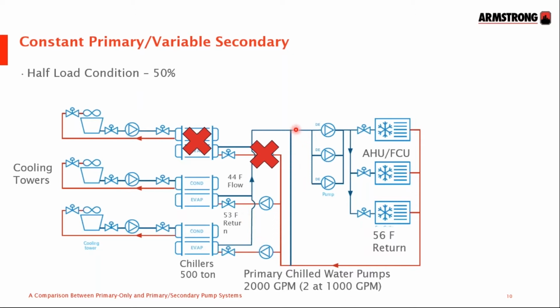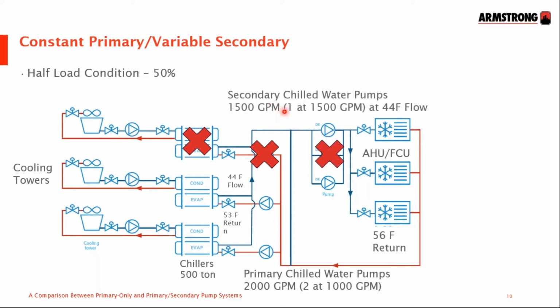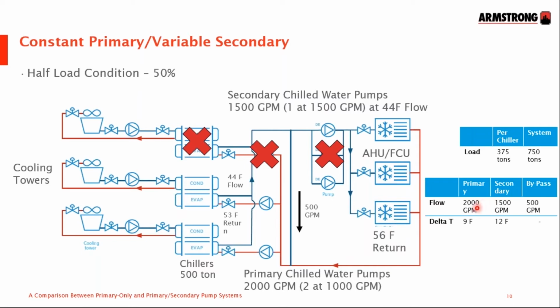The secondary pumps, which are variable speed, of course, slow to 50% of flow, and we take out 1 pump, so there's 1 pump running at 1500 gallons a minute that flows to the coils, warming that water from 44 to 56, maintaining a 12-degree delta T across the zones here. And then the bypass line will have the difference between the primary and the secondary, which is 500 gallons a minute, pumping through the mixing header, mixing with the return water, heating it up to 53 Fahrenheit. So once again, we have that 9-degree delta T with the chillers working off their peak efficiency.